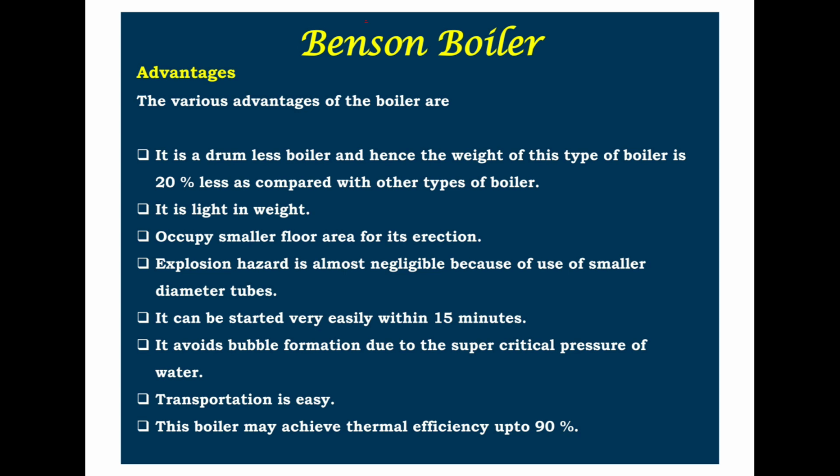Explosion hazard is almost negligible because of the use of smaller diameter tubes. It can be started very easily within 15 minutes. It avoids bubble formation due to the supercritical pressure of water. Transportation is easy. This boiler may achieve thermal efficiency up to 90%.